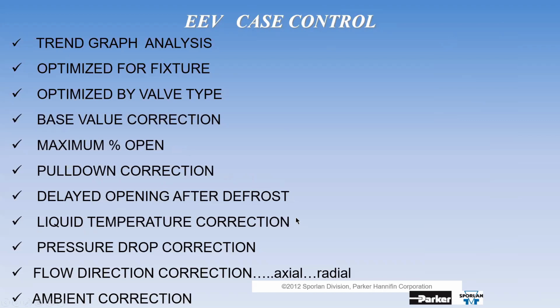Why do I use that? Low temp cases, subcooled. I find out after I build the store that I really have 50-degree liquid coming to this case. Or conversely, I find out that my subcooler is not operating as well as I thought, and I designed my store with a 50-degree liquid input, but by actual measurement on the job site, the best I can do is 65-degree liquid coming to that case controller. I can correct for that. You can't do that with a mechanical expansion valve. You can do that with a case controller and a stepper valve.